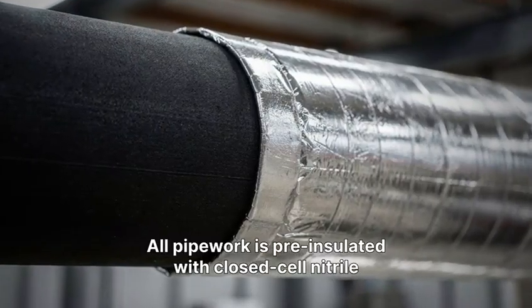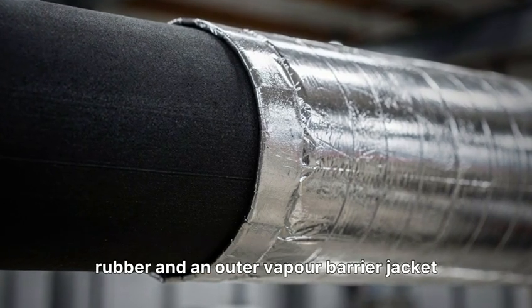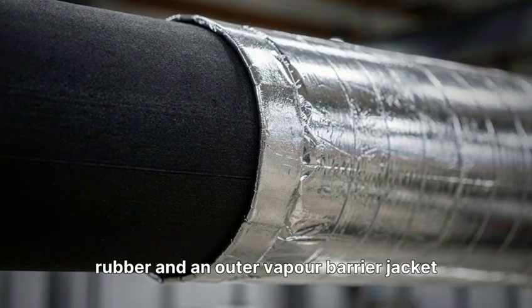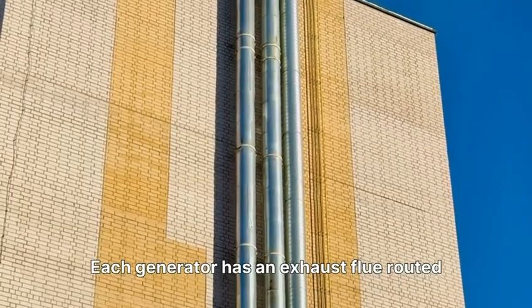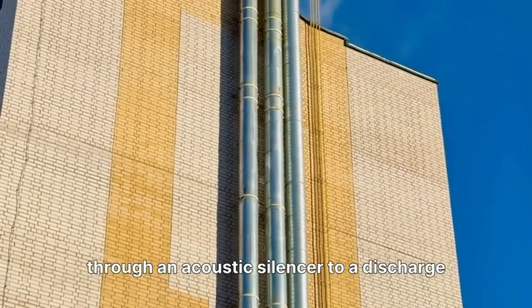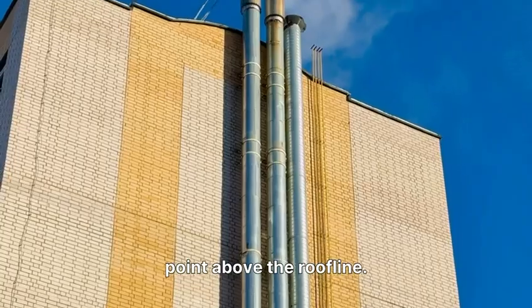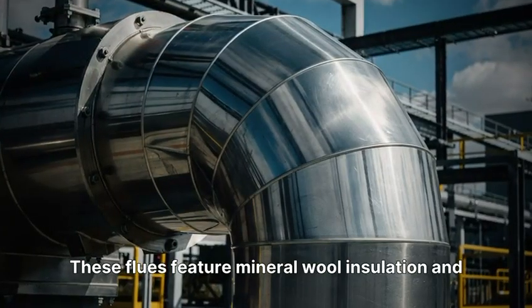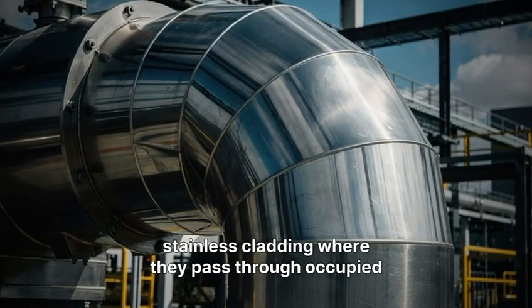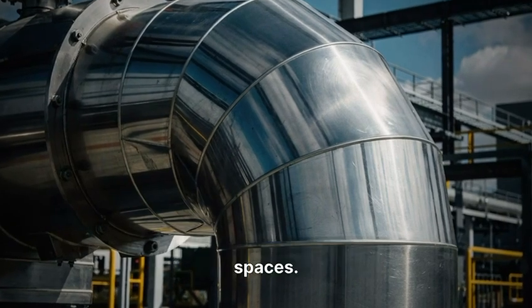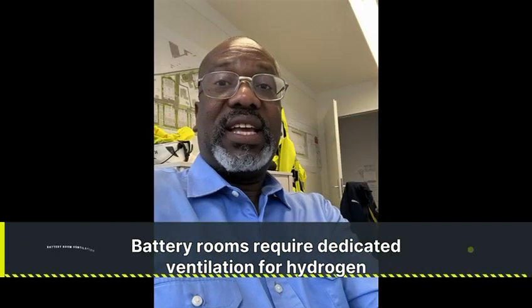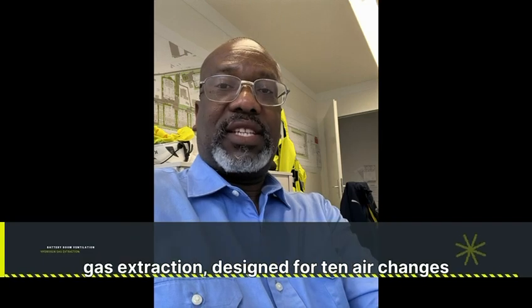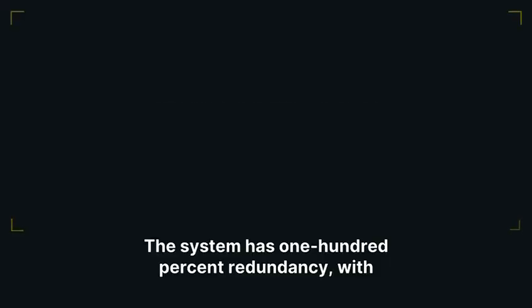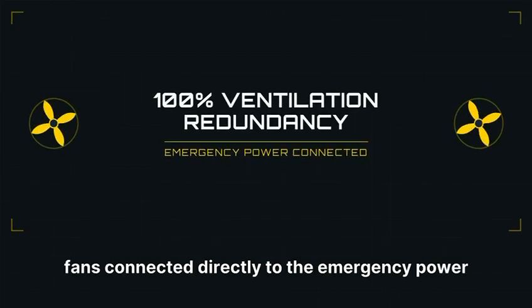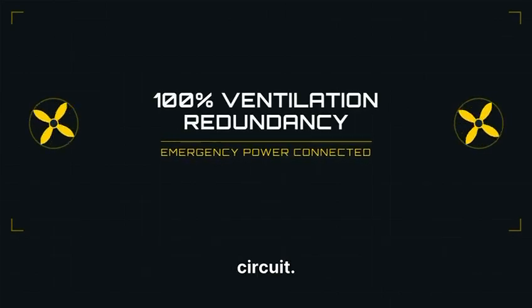All pipework is pre-insulated with closed-cell nitrile rubber and an outer vapor barrier jacket for protection. Each generator has an exhaust flue routed through an acoustic silencer to a discharge point above the roofline. These flues feature mineral wool insulation and stainless cladding, where they pass through occupied spaces. Battery rooms require dedicated ventilation for hydrogen gas extraction, designed for 10 air changes per hour minimum. The system has 100% redundancy, with fans connected directly to the emergency power circuit.